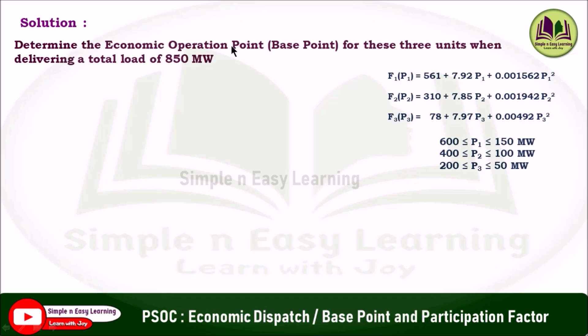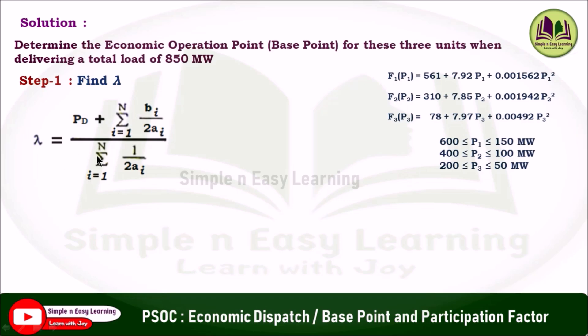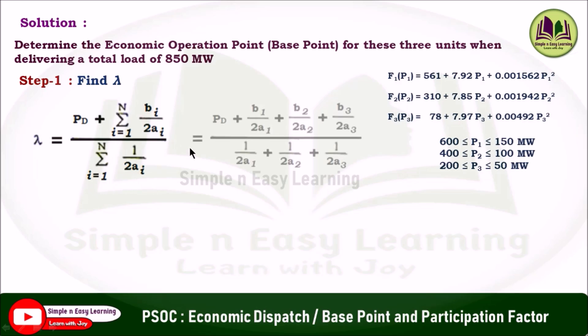Step 1: Find lambda using the formula — lambda equals (Pd + summation of bi/2ai for i=1 to n) divided by (summation of 1/2ai for i=1 to n). Here n equals 3, so i varies from 1 to 3. The formula becomes: Pd plus b1/2a1 plus b2/2a2 plus b3/2a3, divided by 1/2a1 plus 1/2a2 plus 1/2a3.